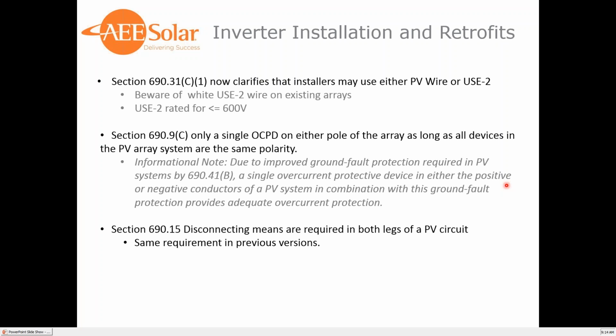One other quick side note, with USE-2 wire, verify that your glands and your strain release on your MC4s are correct for the jackets. Typically, PV wire, with it being double insulated, has a larger jacket diameter, which means that MC4s, if they fit PV wire, might not necessarily fit USE-2, which would lead to water ingress. So be aware of that with your MC4s and your strain release.